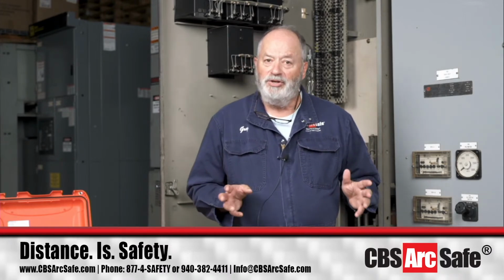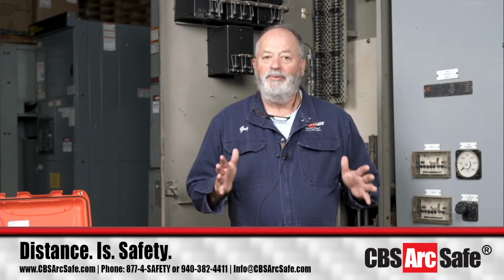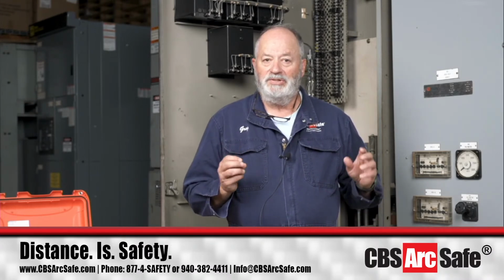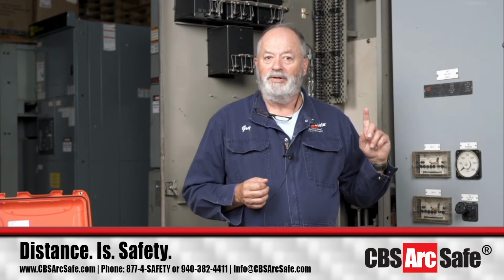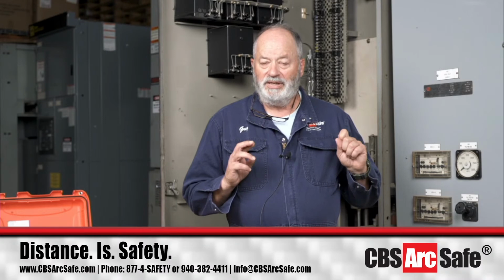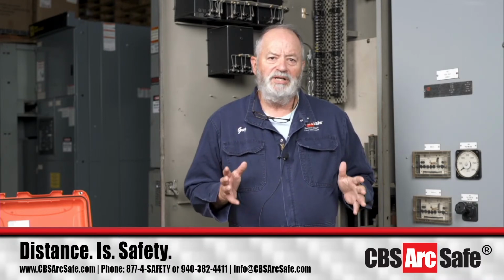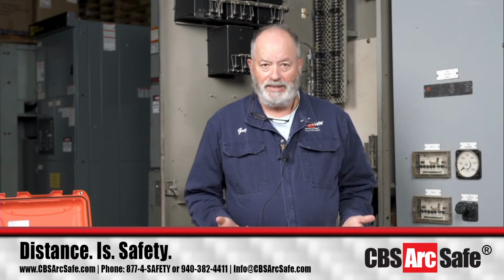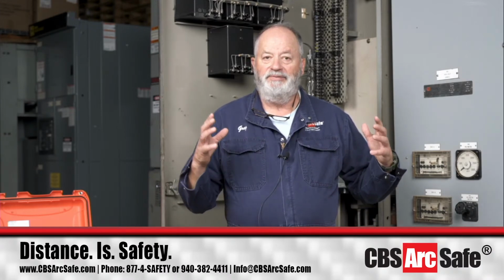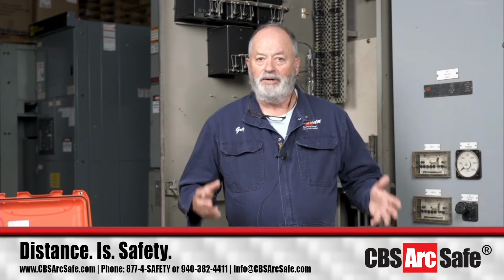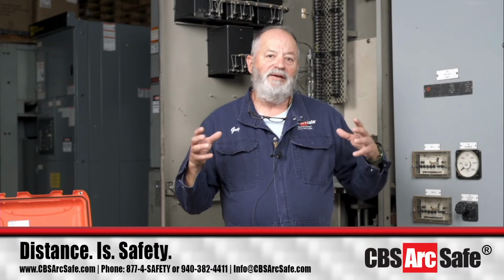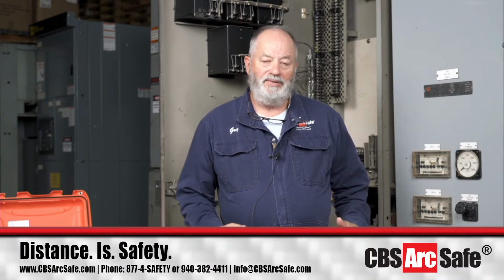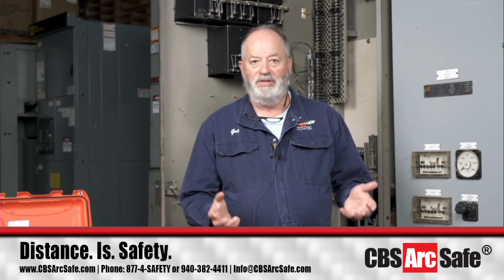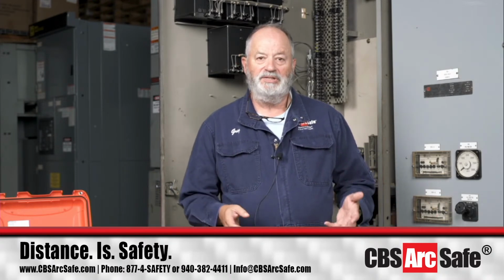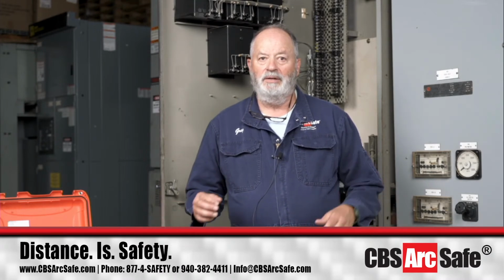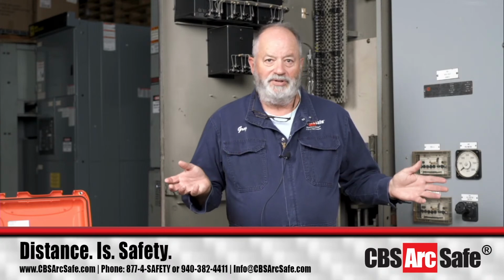Some of the things to note about vacuum retrofits: if you're going to get something done like that, I would encourage you to contact our sister companies, either Circuit Breaker Sales in Gainesville, Texas, or Circuit Breaker Sales in New England up there, Northeast, because when you get a retrofit done for a Magnablast, the breaker has to be weighted. Okay, and if it's not weighted, you can have a 3,000 amp breaker that you've racked up into place, and now it doesn't have enough weight to come down. Okay, and then you have to shut down a bus. You've got to add weights to the bottom of the breaker to get it to pop off the tulips to get this thing to come down, and then you've got to send it back to get the weights put on by the people that did the retrofit because they didn't do it right.